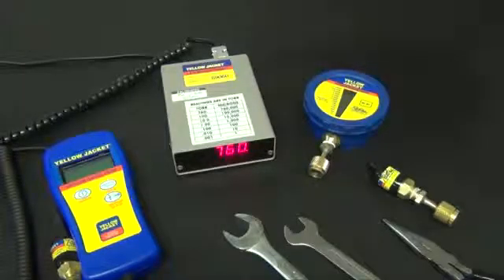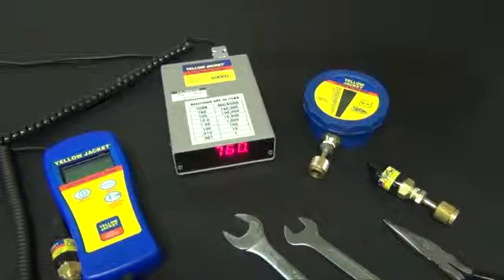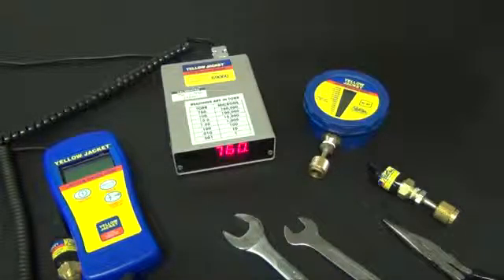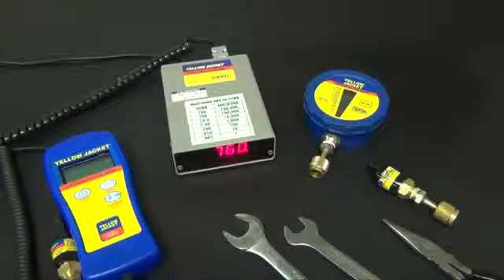The last thing that you can do is hook your vacuum gauge up directly to your vacuum pump. Most pumps will easily pull 50 micron. If you are getting a high micron reading on your vacuum gauge, your sensor is contaminated with oil. We have a manifold tree on our pump so that we can run our certified test gauge against the vacuum gauge that has oil contamination in the sensor for comparison.